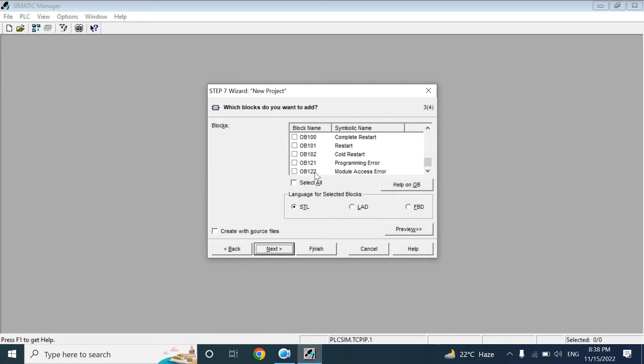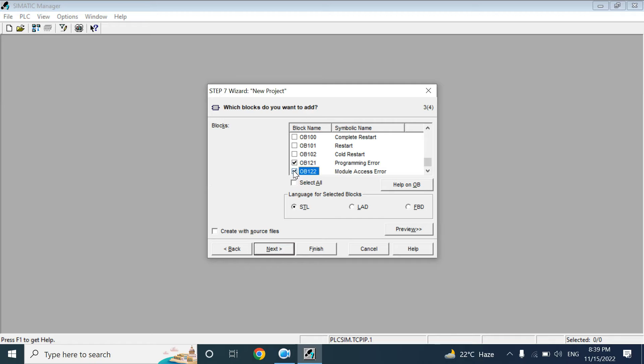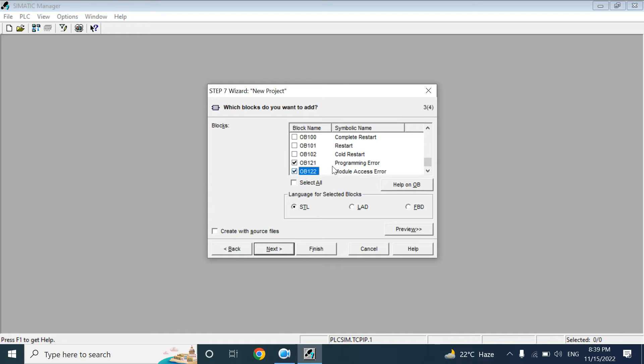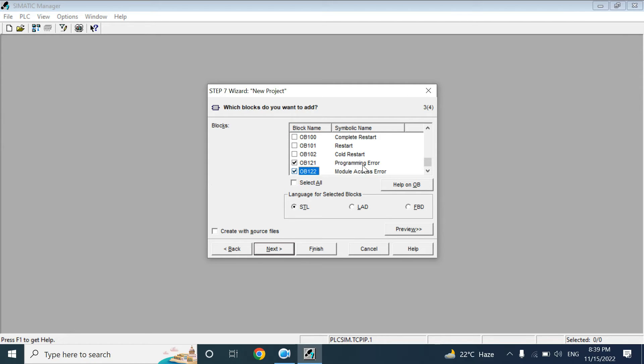But I always add two organization blocks: one is OB121, another is OB122. Because in some cases, if your program has some error when you download, it will not stop the download. It will take the download of your program. If you take OB121, the CPU will not stop. It will show the error, but your CPU will be in run mode and your process will run.